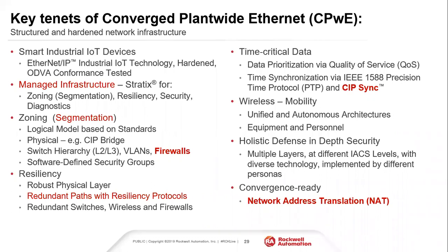We typically don't see this on the process control network side of it, but we do something called CIP Sync, or time synchronization. The biggest reason why this is important for you guys is if you've ever tried to have an alarm system and you have multiple alarm systems all throughout, if they're all on a different time base, all of your alarms are messed up. So typically on the computer side of it, a domain controller will send the time synchronization to every single computer that you have on the network so that they're all matched up and everything's tied in. But if anybody's ever gone to your PanelView or to your controller, a lot of the times the wall clock that's on there is all messed up.